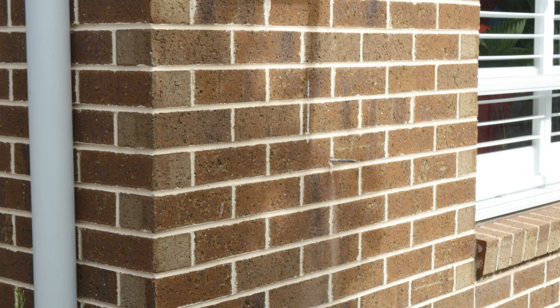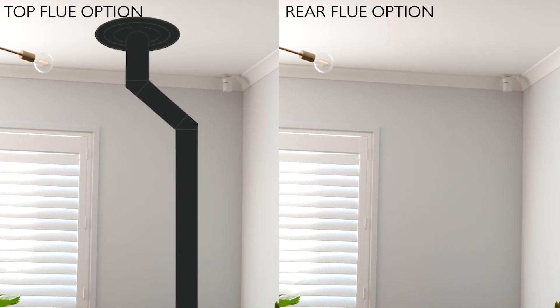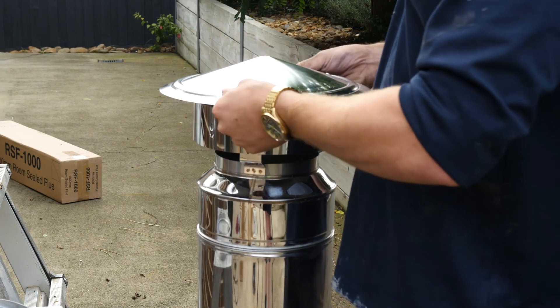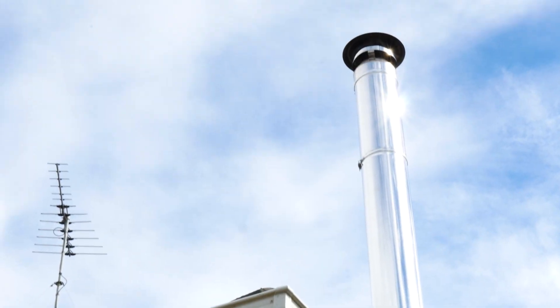We've come up with a completely great solution to have this heater installed in this home. Rather than having ugly bends in the room, we're able to put a rear flue on the back of this heater, penetrate through the wall, and using the insulated room sealed flue kit, we now have a flue going up the side of the home, well out of the way.